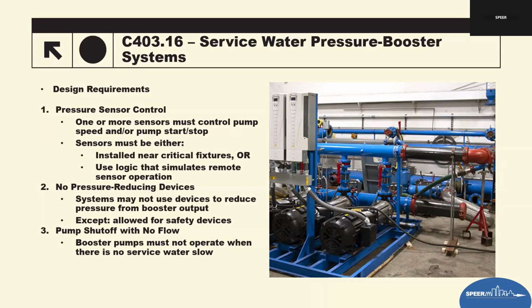Plan reviewer tip: confirm the control sequence shows pressure-based VFD control or pump cycling. Verify sensor placement and logic or simulation strategy. Look for any prohibited PRVs installed downstream from the booster pump. And then review pump schedules for standby and duty configurations. Field inspection: confirm sensors are installed as shown in the submittals.